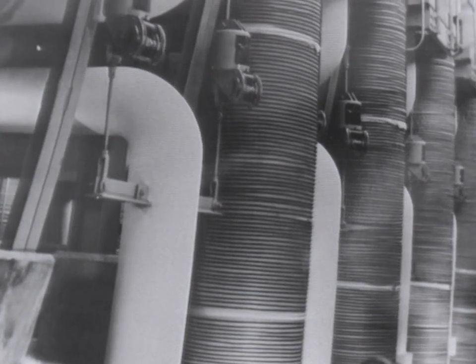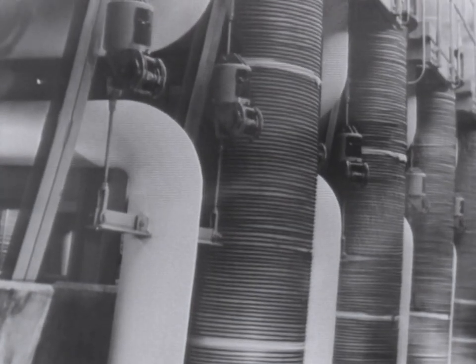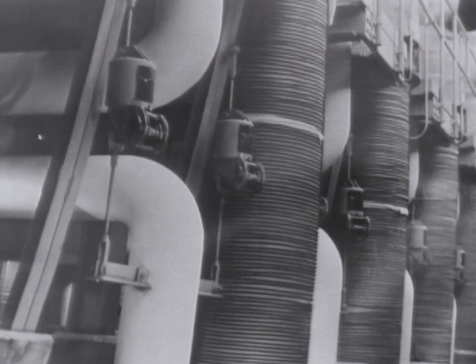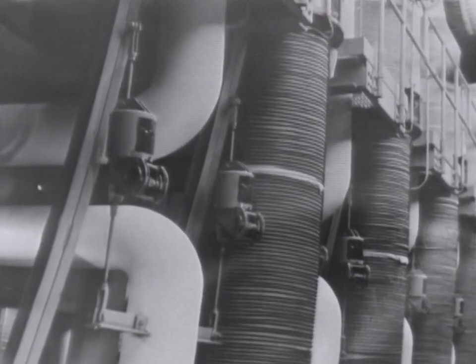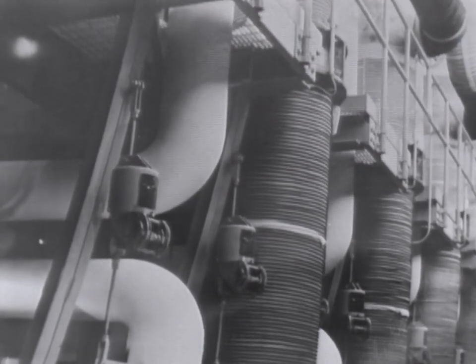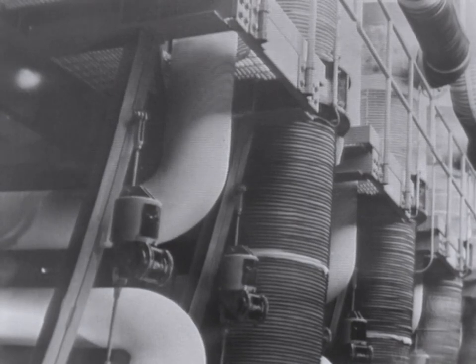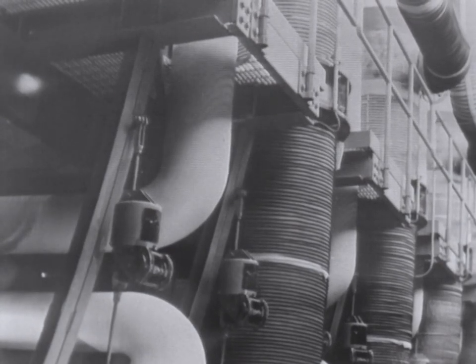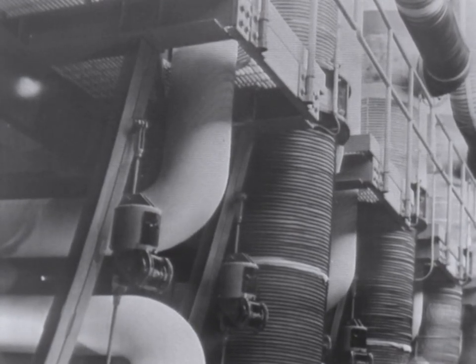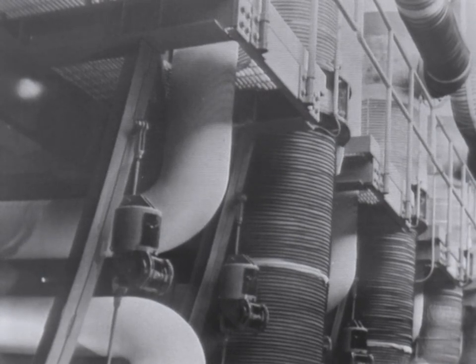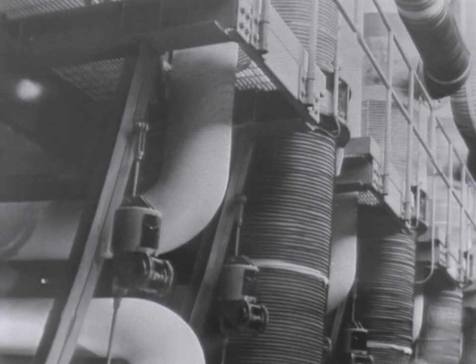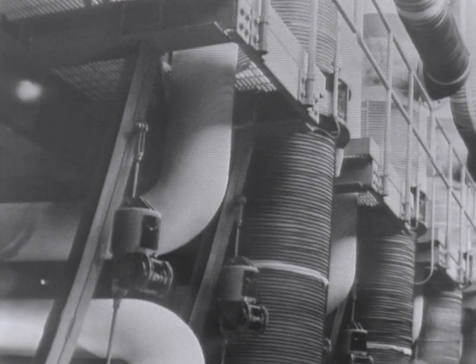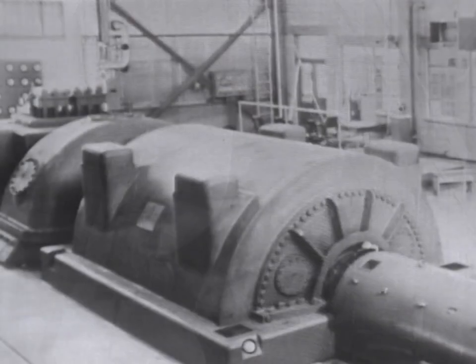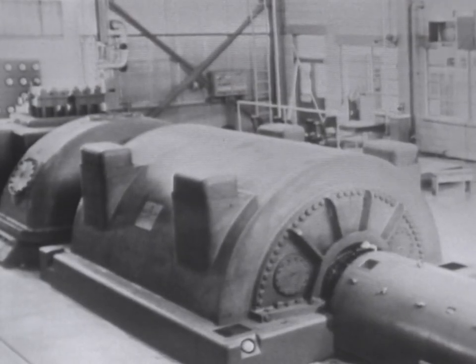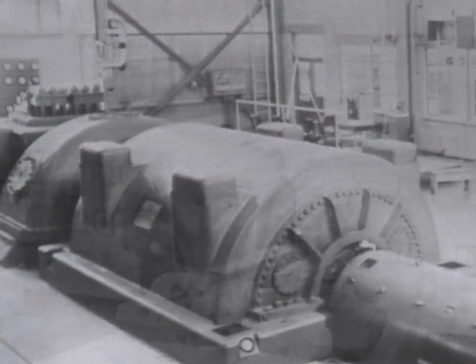It is. Basically, it's just another series of heat exchangers. However, these exchangers are of highly refined, very sophisticated design. In these units, heat is transferred from the secondary system sodium to water to generate steam at a temperature of about 840 degrees Fahrenheit and a pressure of 1,300 pounds per square inch. The steam then flows to the turbine generator located just outside the control room.